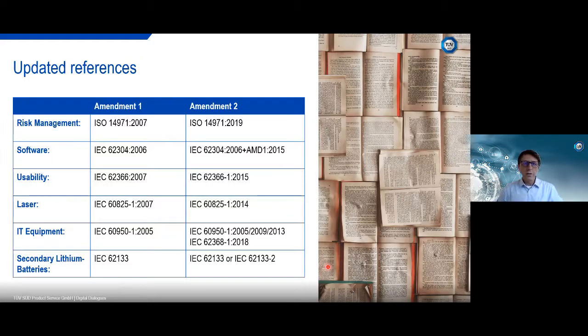Let's also look at the references updated in Amendment 2. Basically all references that were no longer up to date were updated. You can find an overview in this table: here are the references of Amendment 1, and here the references of Amendment 2. You can see that for risk management, the references to software development, usability, lasers, IT equipment—which I mentioned before—and also secondary lithium batteries have been updated, and the correct reference can now be found in this table.